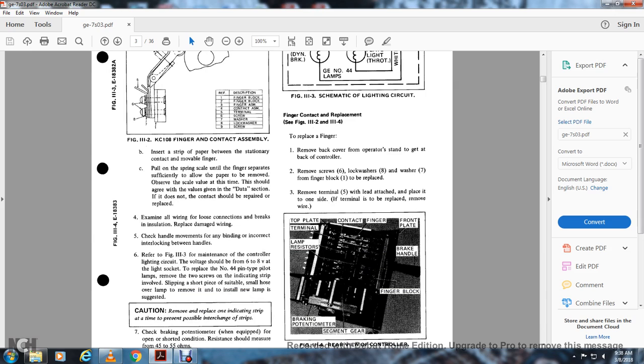Pull on the spring scale until the finger separates sufficiently to allow the paper to be removed. Observe the scale value at this time. This should agree with the values given in the data section. If it does not, the contact should be repaired or replaced.